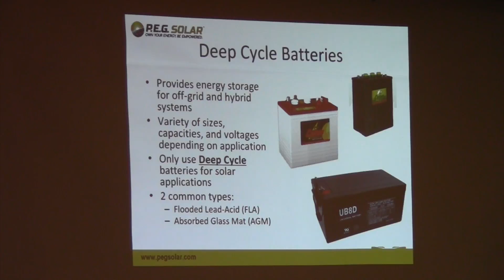You were talking about enclosures. If you keep batteries outside near the house, do you keep them in some sort of well-built wooden storage cabinet? Yeah, because you're not supposed to set batteries on metal or anything like that, correct? Often for larger battery banks we'll build an enclosure adjacent to an exterior wall, framed out just like an addition, with siding and 1-inch foam insulation inside for thermal insulation. Then we'll run a conduit between the box and wherever the inverter is placed to bring the conductors through.